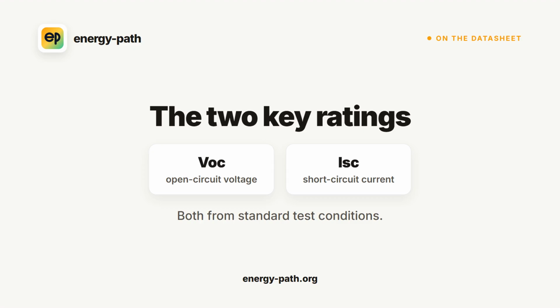A safety reminder follows from this. A disconnected string still has its full open circuit voltage, and in cold weather that voltage is even higher than the label. Always measure before you trust it.